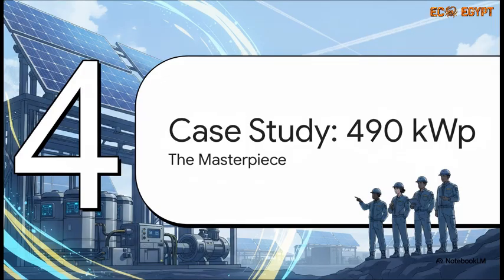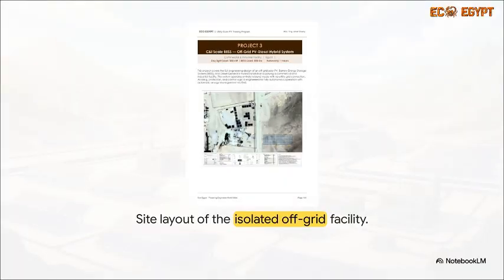Let's move to Section 4, the case study. Time to look at our 490 kilowatt peak masterpiece. Let's actually put all this design theory into practice on a real commercial and industrial facility. This system operates entirely in island mode, zero utility grid connection. The engineering drawings delivered for this project had to be flawless, accounting for massive physical footprints and incredibly precise control diagrams. When you're building fully autonomous energy management, there's just no room for error.